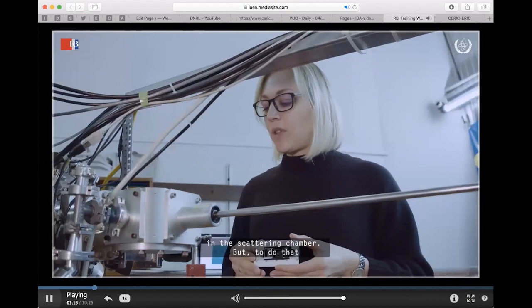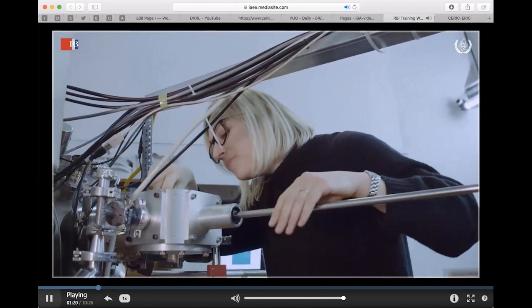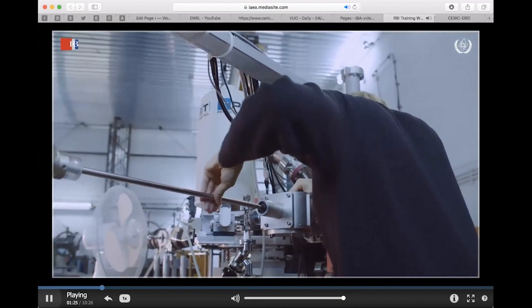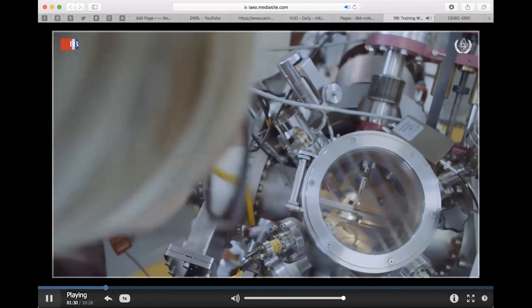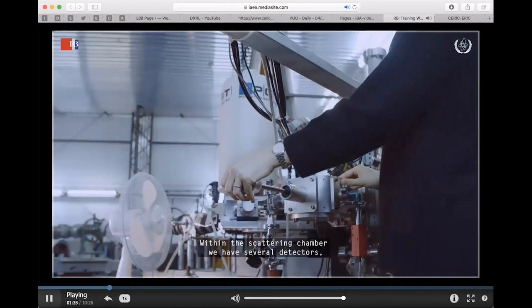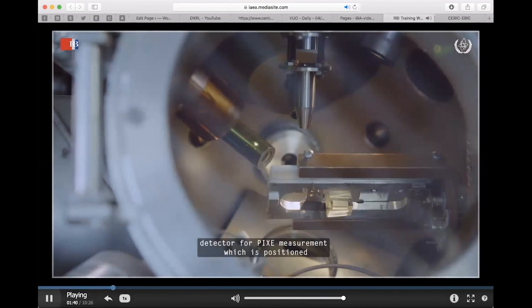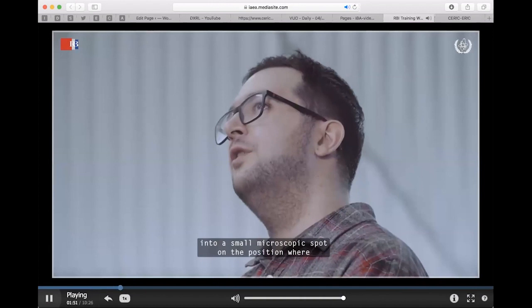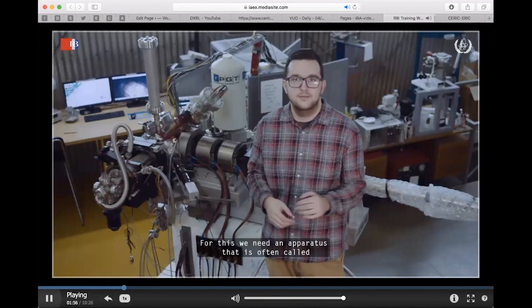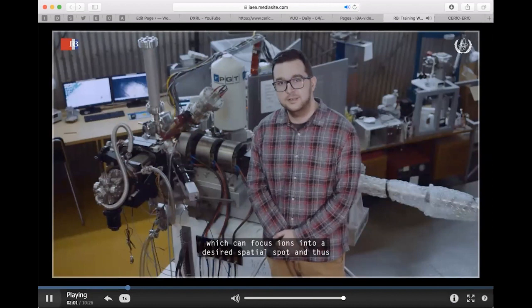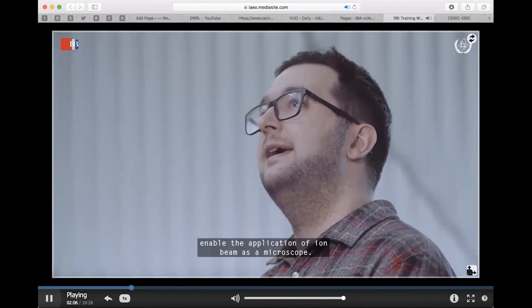Before the measurement, we need to mount the samples onto a universal sample holder and load it in the scattering chamber, first mounting it in the load lock pre-chamber. Within the scattering chamber we have several detectors, and for this experiment the most important one is the X-ray detector for PIXE measurement, positioned in a backward angle at 45 degrees. The main prerequisite to perform an ion beam microscopy measurement is to focus an ion beam into a small microscopic spot on the sample position — this requires a nuclear microprobe, which can focus ions into a desired spatial spot.